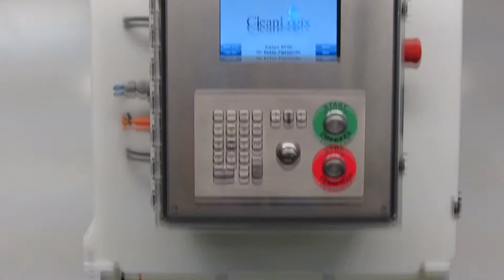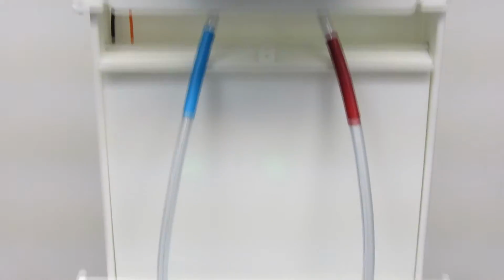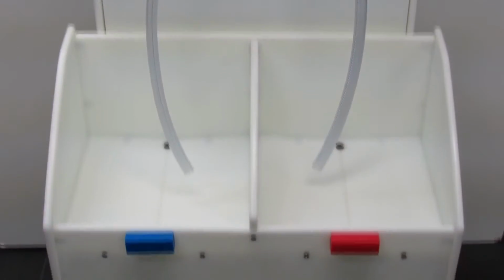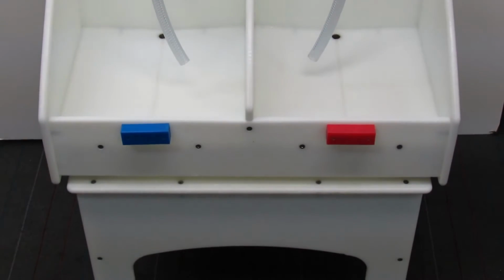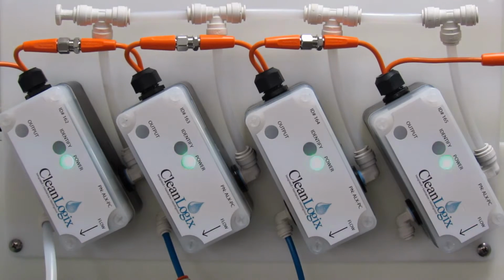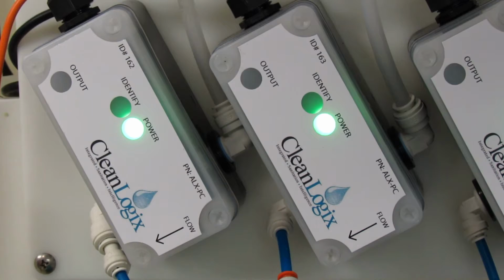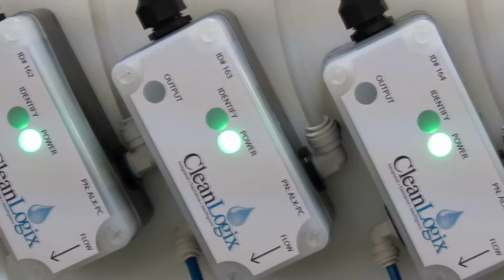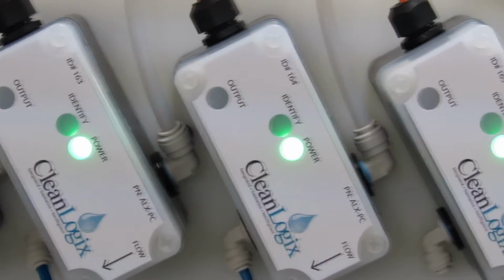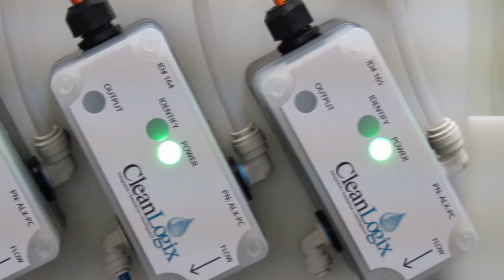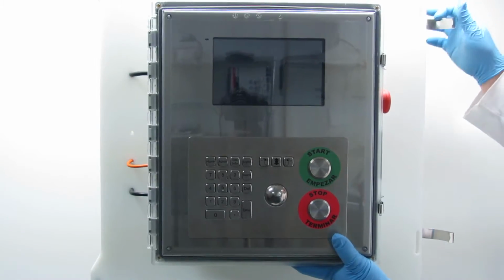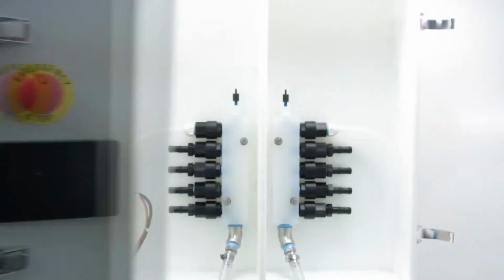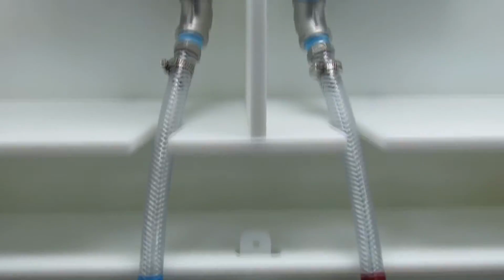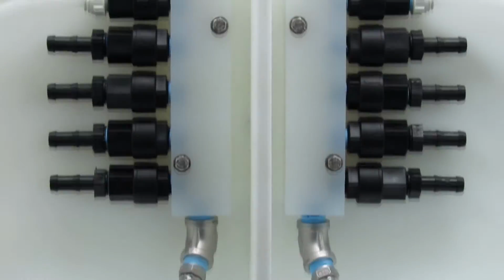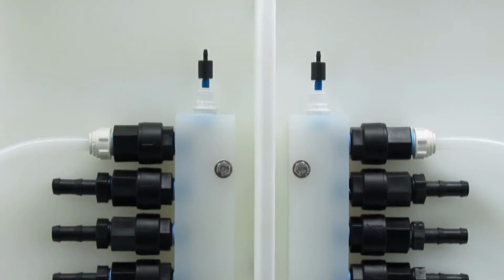A scale ensures the correct amount of chemical is being dispensed, while the dual jug scale tray prevents acids and caustics from mixing. The pump controllers are mounted next to the pumps to provide an air supply to each air-operated pump. Comprised of a small circuit board and solenoid, they are extremely flexible and easily expandable to accommodate any number of pumps. A dispense manifold mounted behind the control box allows for compatible chemicals to be dispensed through one hose, dispensing acids through one manifold and caustics through another.